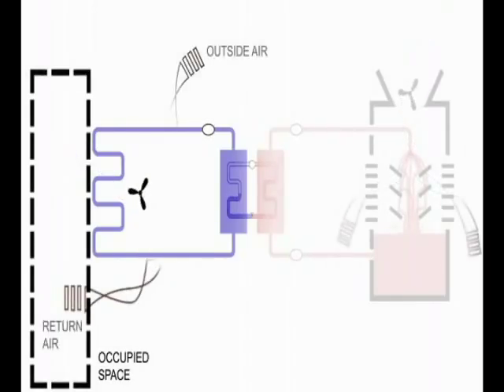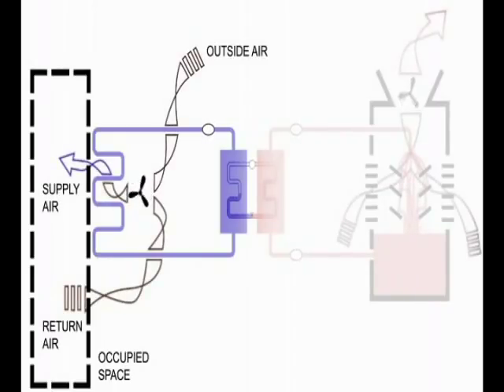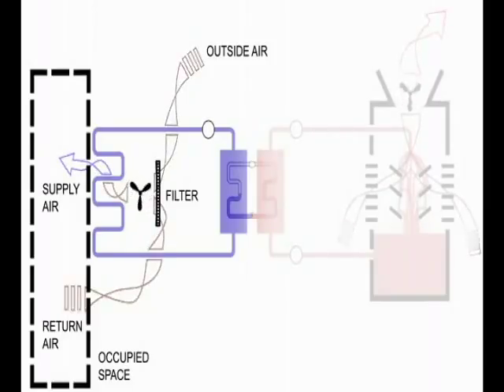Outside air is introduced into the air loop, and that outside air combines with recirculated air from the room before both volumes of air move across a filter. Of course, simply adding lots of outside air without exhausting some of the inside air is not stable.